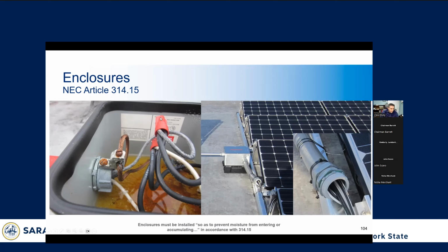And on the right, we have a situation where we have conduit. This is a flat roof with solar panels installed on it. We have conduit coming out of this junction box, and it goes up so that the wires can go over the racking system. But when you have a situation like that, rain can just get right into this hole, and then it just drains right into the enclosure. So that provides like a highway for water entry into the electrical enclosure, which again, you always want to avoid.